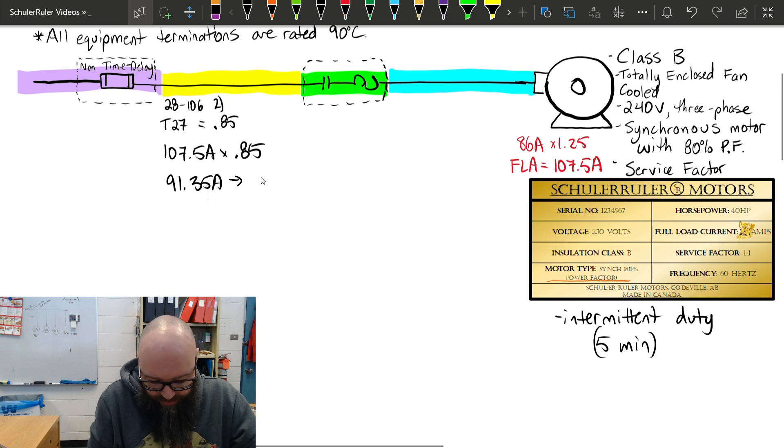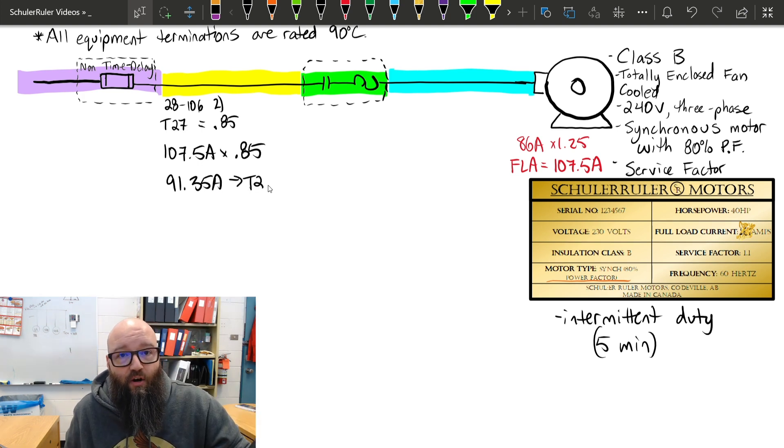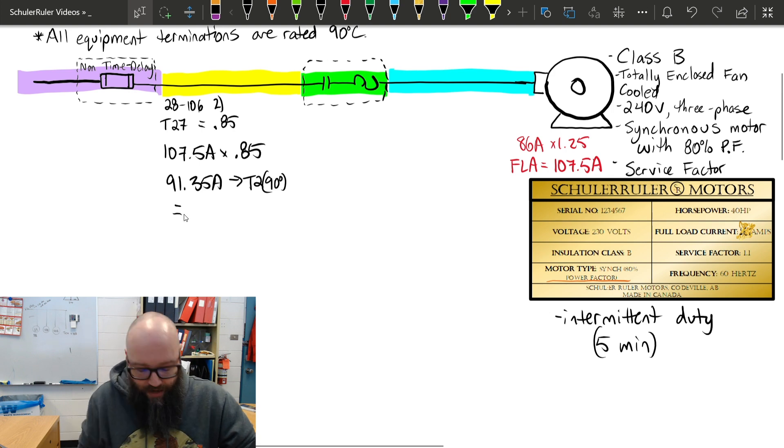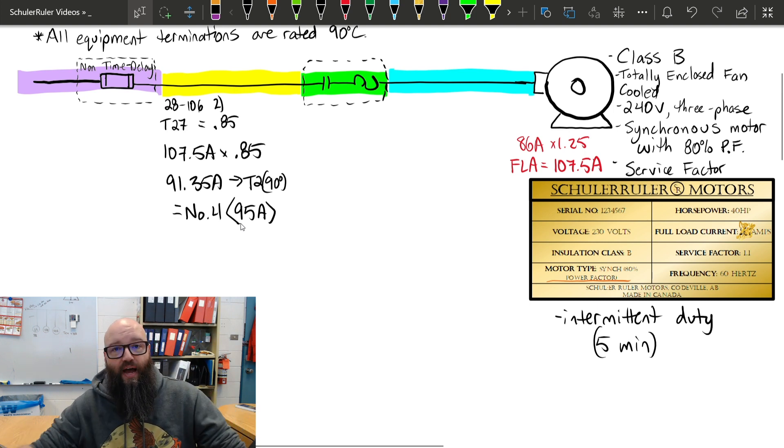We're going to take that to table 2. Because it says up at the top that our equipment termination temperatures are 90 degrees, I'm going to use the 90-degree column when I go to table 2, which should yield a number 4. That number 4 has an allowable ampacity of 95 amps. That'll safely handle that 107.5 amps at that 85%. So that's our branch circuit conductor.